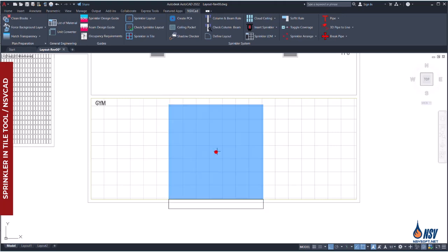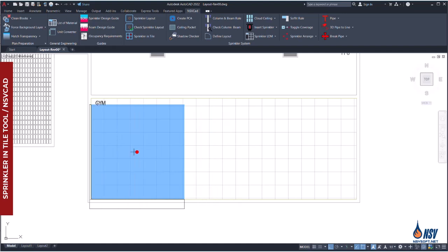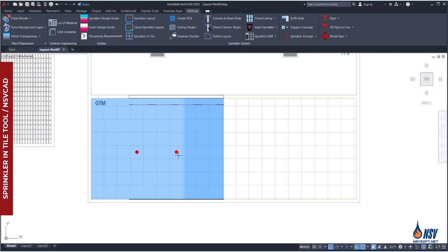When the small room rule is applied, the software extends the sprinkler's coverage area on one side to reflect the adjusted spacing allowance. By pressing the R or L key, we can rotate the sprinkler to the right or left in order to find a position that fully covers the room's width. Taking into account the CS label next to the sprinkler, which indicates a cold soldering risk, we determine the placement of the next sprinklers accordingly.